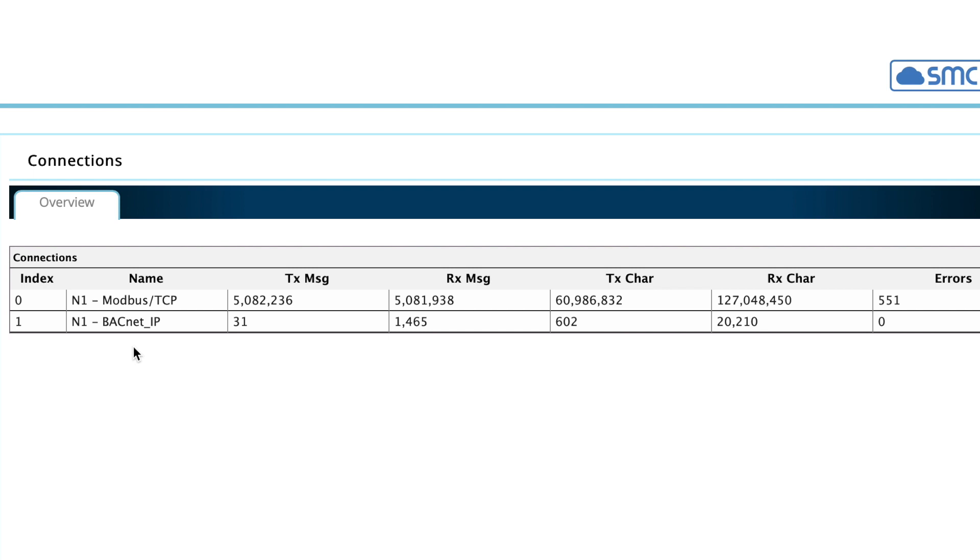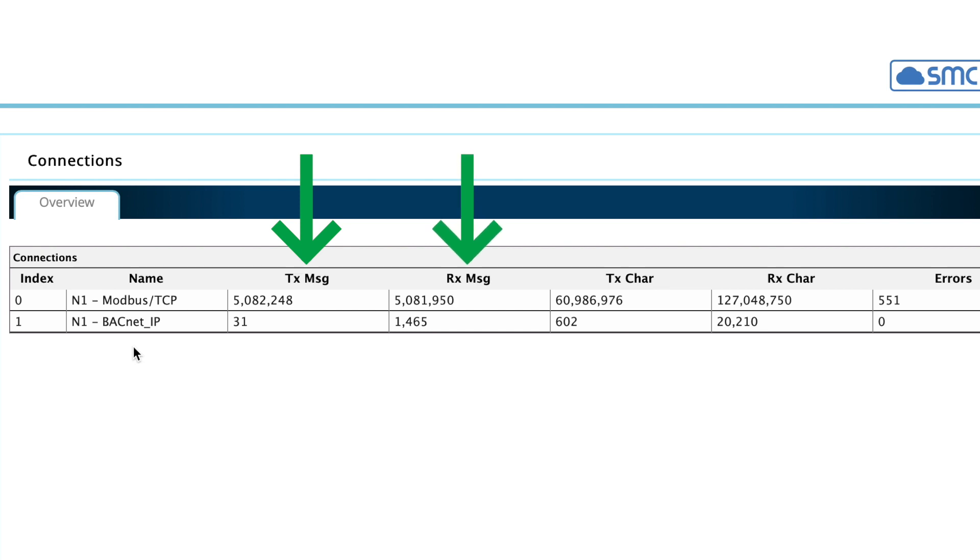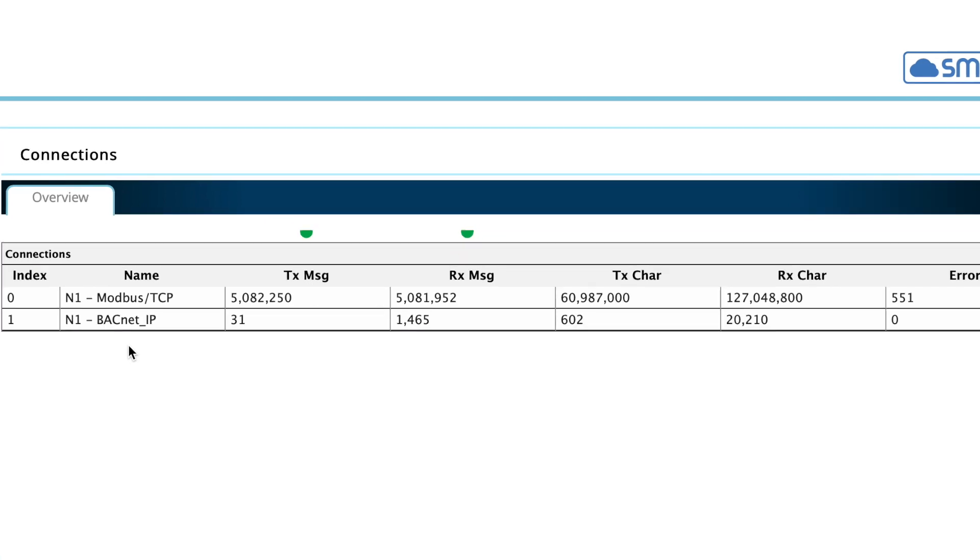First, check Index 0. You want to make sure that good communications and data are being sent to the Protonode from the field devices. Check the TxMessage and RxMessage columns in the Connection Overview. In an ideal integration, both columns will be constantly incrementing.